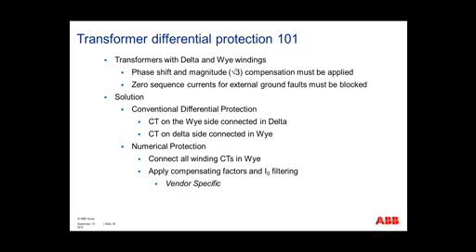If you have a microprocessor-based relay, you can do this via settings inside the relay. If you have a Delta-Wye or a Wye-Delta connected transformer and you're using a microprocessor-based relay, you can connect all your CTs in Y. Once you've done that, there is typically a setting, and different vendors do this differently, for how to filter the zero sequence currents from your differential.